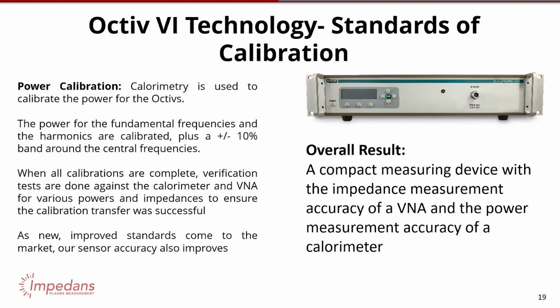Okay, and then of course you need to do a power calibration, and typically you use calorimetry for that. So for our sensor, we calibrate at the fundamental frequencies and the harmonics, and also a band around the frequencies, because these days you use what's called frequency agility for fast tuning. And when all these calibrations are complete, you must then verify that the calibration was successfully transferred to the unit. So you have to do verifications afterwards at different loads, different powers, and so on to make sure it's good.